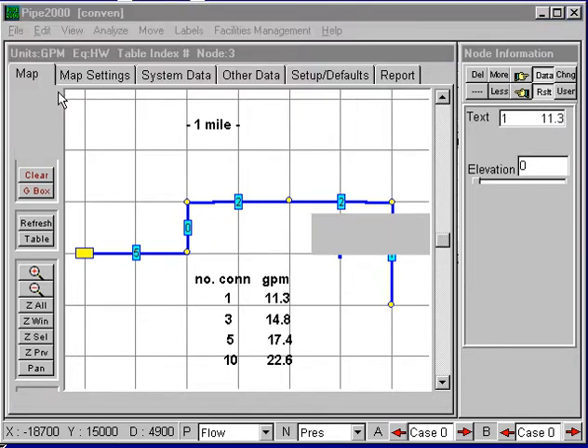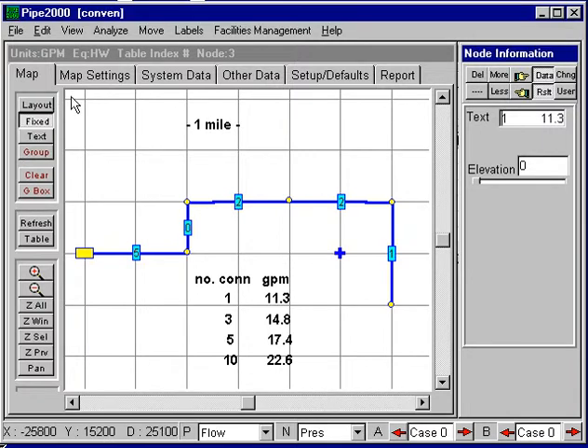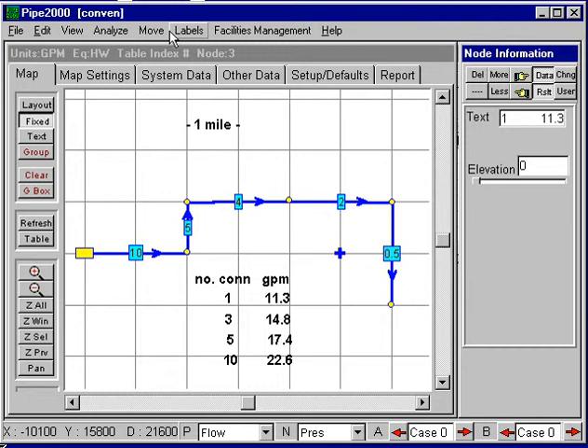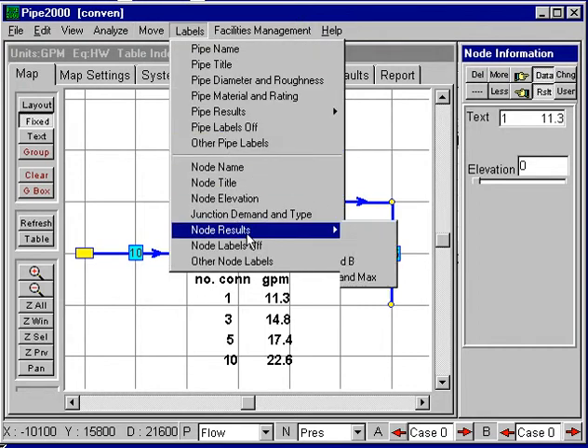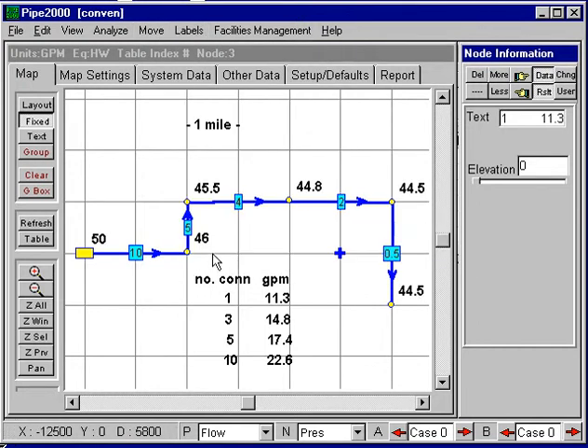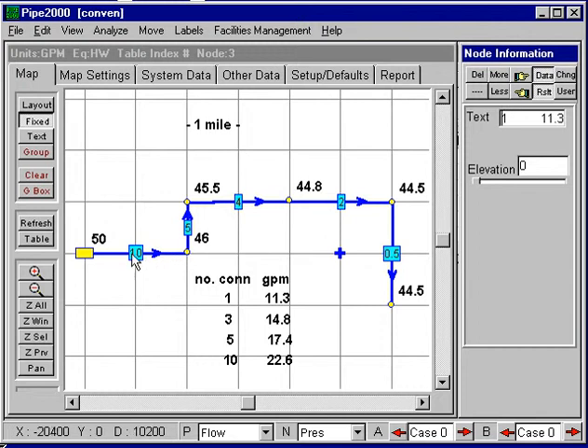Now we're going to go through and do a conventional analysis. We analyze the system, and I'm turning on the information — the flow rates and the pressures. We see now that we have the flow rates we would expect: ten gallons here to serve the ten users, five, four, two, and a half. And the pressures show very little pressure drop.